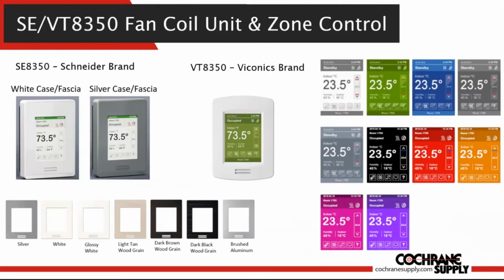Alternative fascias are available to fit in a multitude of installations where the aesthetics have to be perfect. There are versions of wood grain, glossy, and even aluminum. The Viconics version, which begins with the letters VT8350, only comes in a unified white fascia and case combination. With either model, multiple background colors can be selected. Again, background color can be selected from the touchscreen configuration pages, and it's even a BACnet point that can be commanded from a supervisory system.